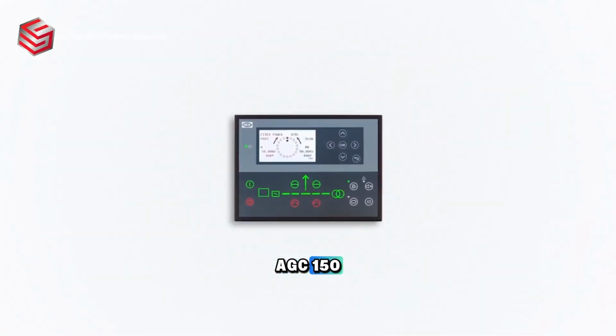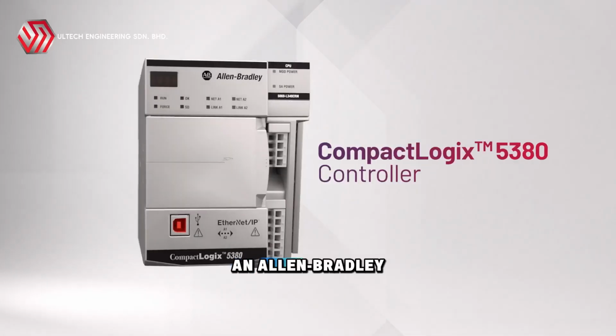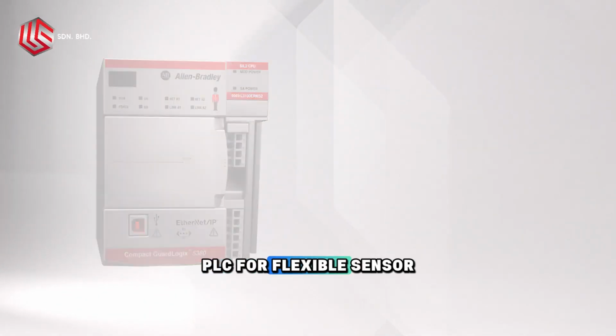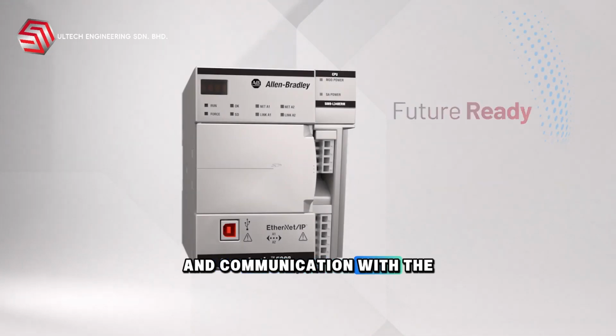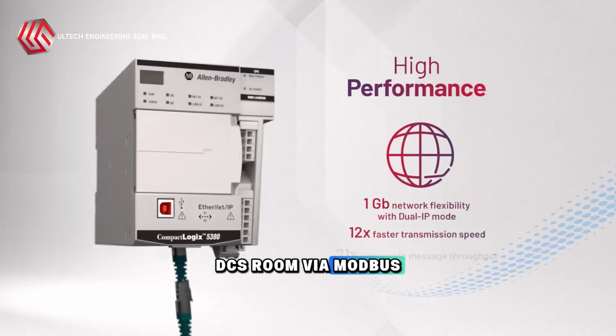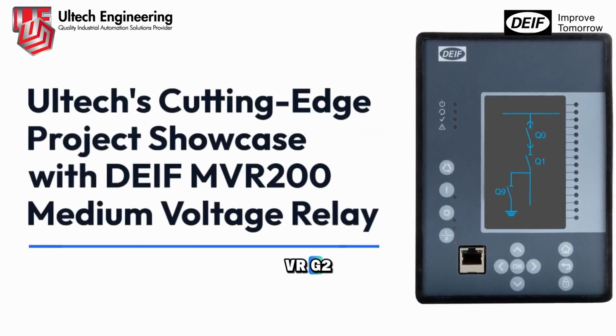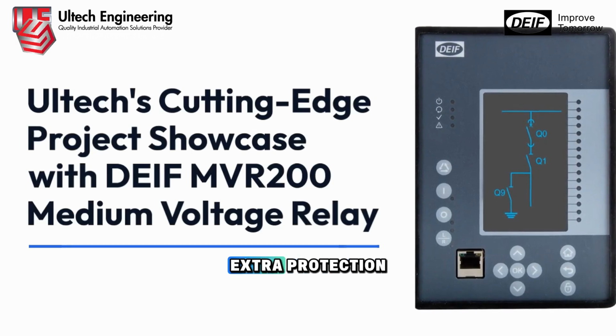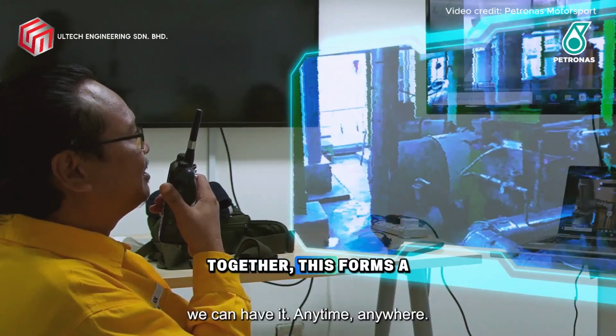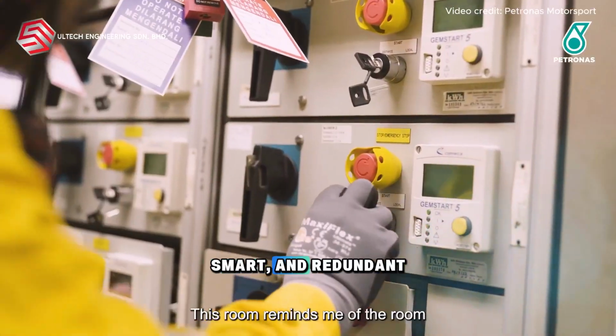On top of that, we integrated the DEIF AGC 150 controller, an Allen-Bradley PLC for flexible sensor monitoring and communication with the DCS room via Modbus, and a DEIF MVR200 relay for extra protection. Together, this forms a highly reliable, smart, and redundant system.